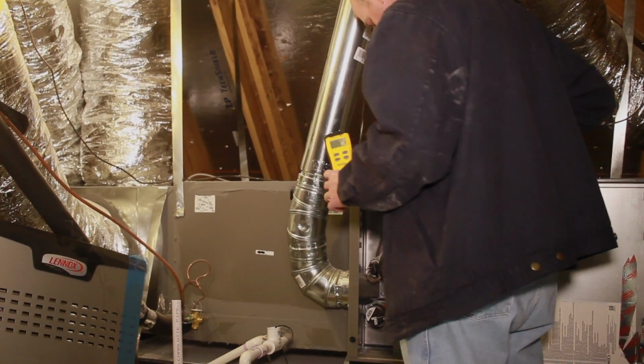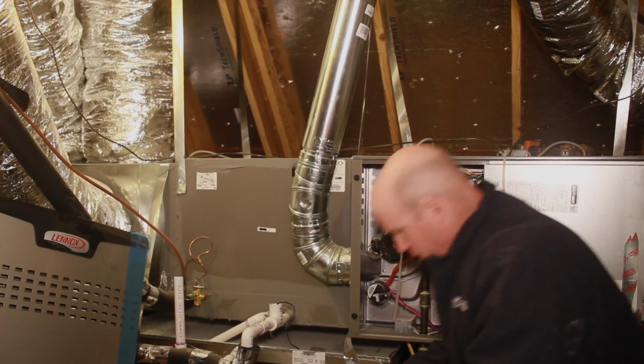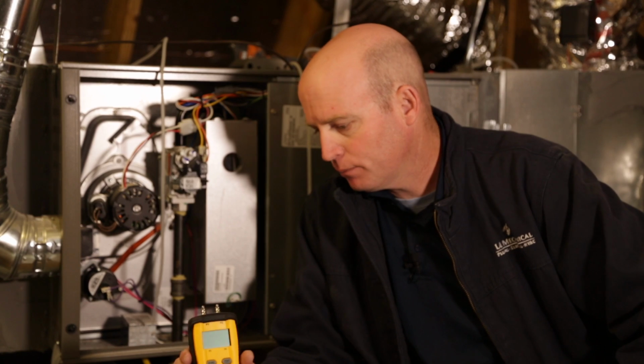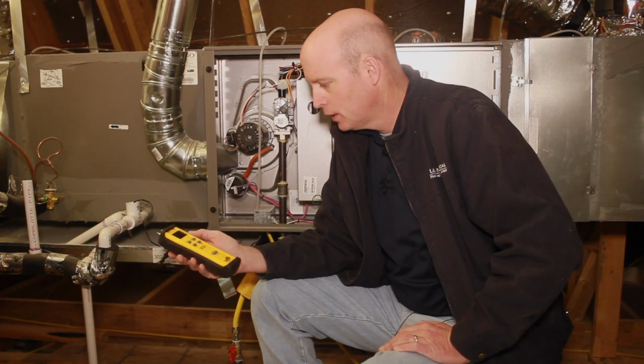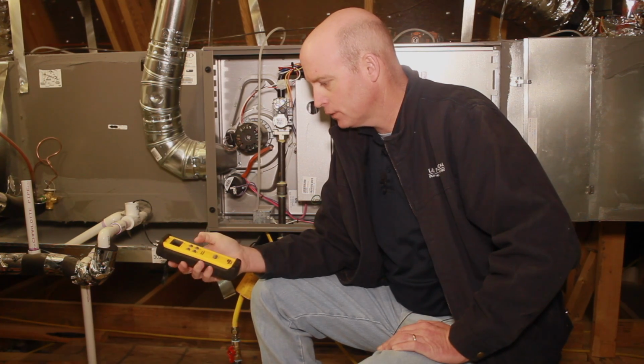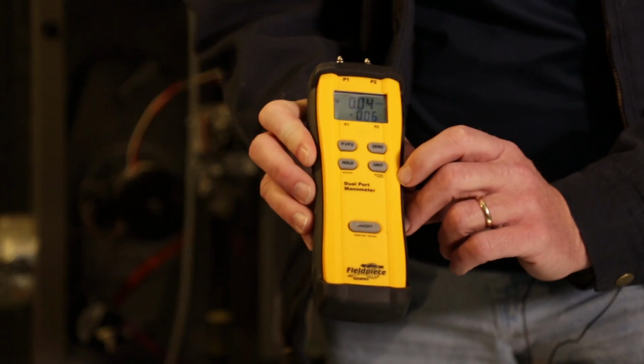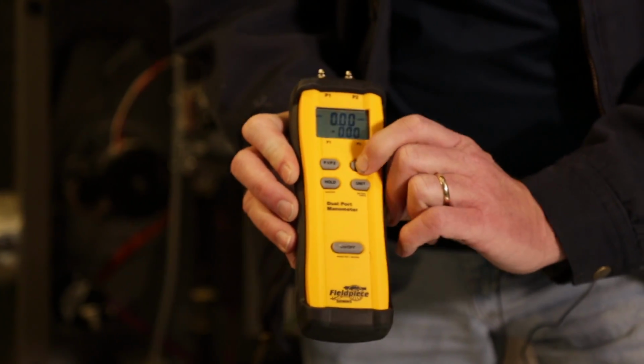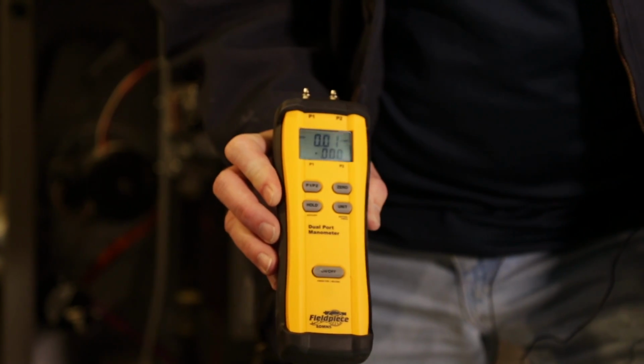The furnace is off. What we're going to do is calibrate our meter. This is very important. You can't plug in your hoses, turn the equipment on, and then turn your meter on, because it will assume that whatever static pressure you have is 0. So we'll turn our meter on. We just hit the power button, and then we're going to hit the 0 button. And that's all there is to it.